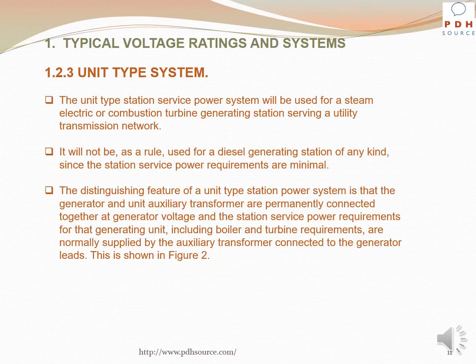The distinguishing feature of a unit type station power system is that the generator and unit auxiliary transformer are permanently connected together at generator voltage, and the station service power requirements for that generating unit, including boiler and turbine requirements, are normally supplied by the auxiliary transformer connected to the generator leads. This is shown in Figure 2.